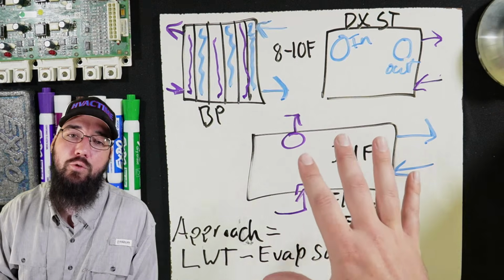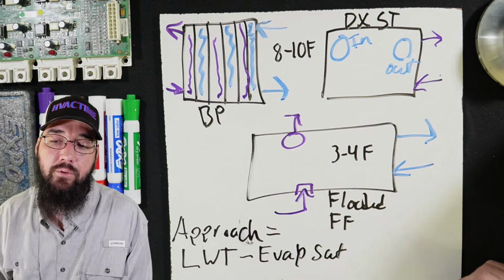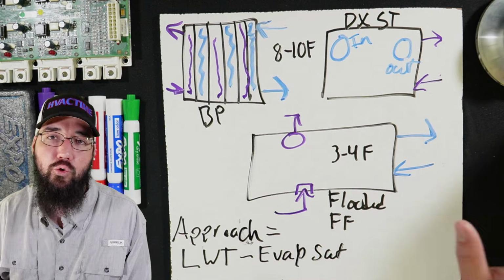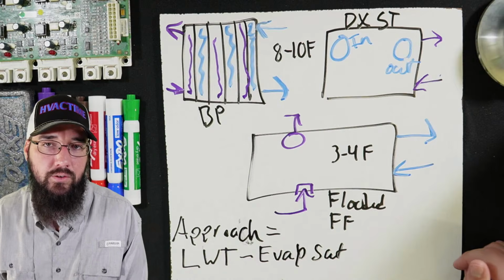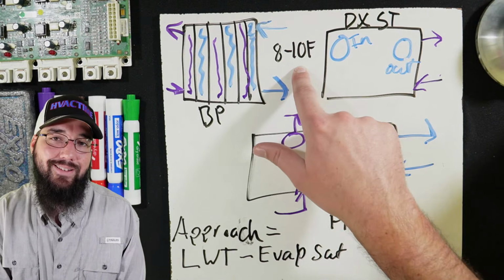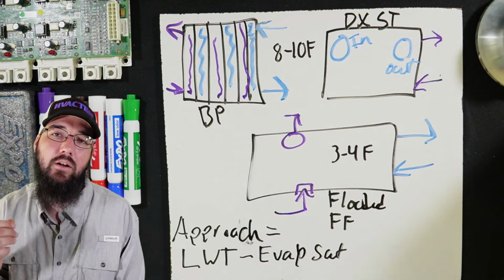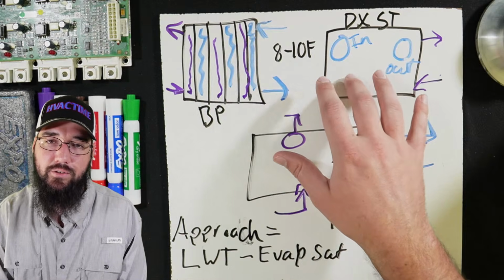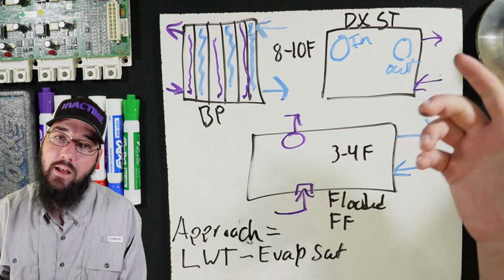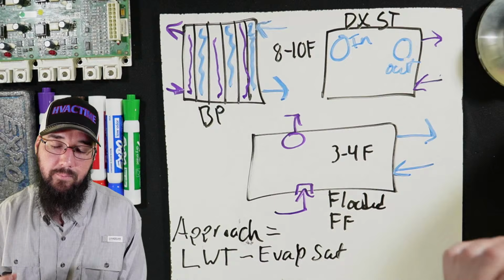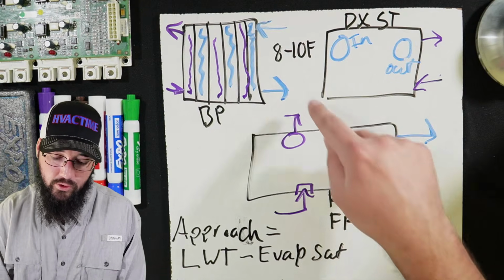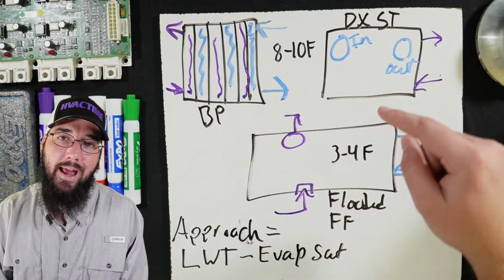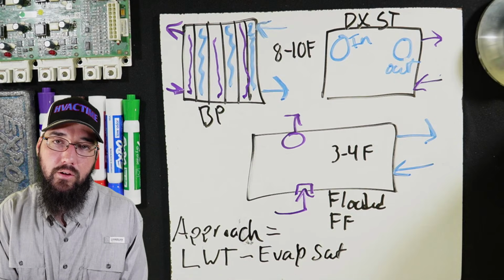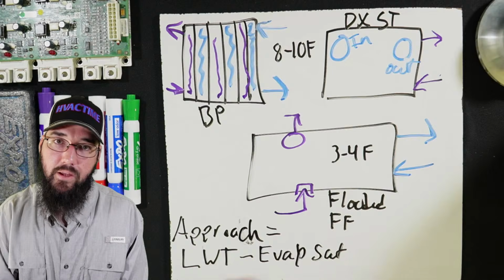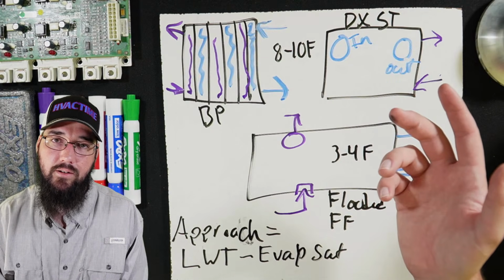But this is how the approach will change and be affected. And if for any reason you do see any tube-in-tube machines, maybe you're working on some small process chillers, those will also be an 8 to 10 typically design approach value. 10 being the most standard for these. Like the vast majority of these will be about 10 degrees at full load. Now keep that in mind from a service perspective. If you are seeing full load approach values at partial load, there's a problem. Investigate that. We shouldn't have that.